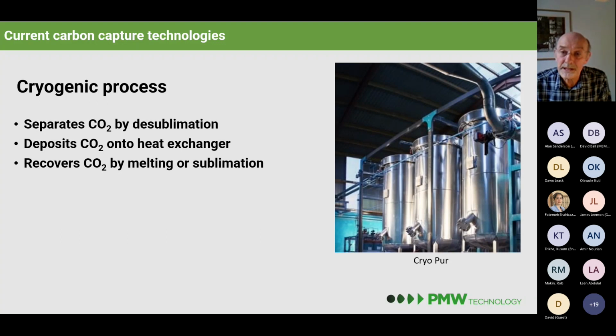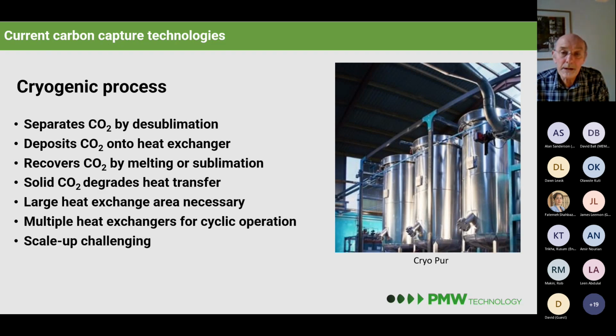So inside our bright stainless vessels on the right, we have heat exchangers onto which the carbon dioxide freezes, just like the inside of your domestic refrigerator. Once the frost has built up too much, you switch them off from absorbing and warm them, perhaps from minus 80, to melt the carbon dioxide off the surface again, warming it to the appropriate temperature to form a gas. However, just as the domestic refrigerator suffers from furring up, these also suffer from it, and the heat transfer degrades, so you need a larger heat exchange area than you might have thought.